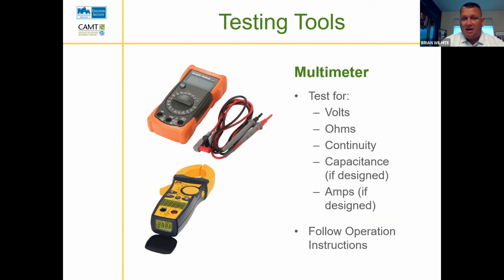On these two meters, the top left one, the orange one, has an amp setting, but in order for me to get the proper amps on that, I have to take those pins and puncture the insulation on the wire to get an amp reading, whereas the one on the bottom has an amp clamp. I clamp it around one wire, and it gives me an amp reading. And so for me, my amp clamp Fieldpiece has everything I need. Now, it also has a detachable clamp, and there are some other things I can buy to add to that meter. I never bought them because I don't really need them, but it's affordable as well. I think it's about $150. It does everything that I needed to do.